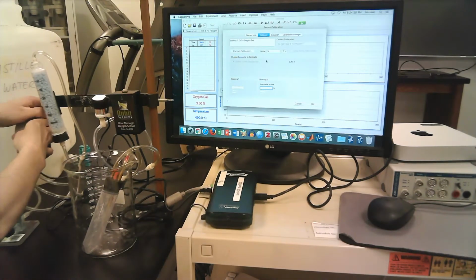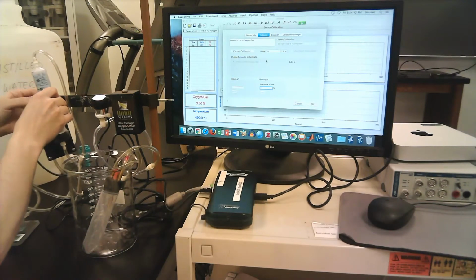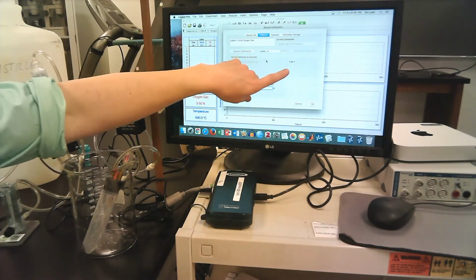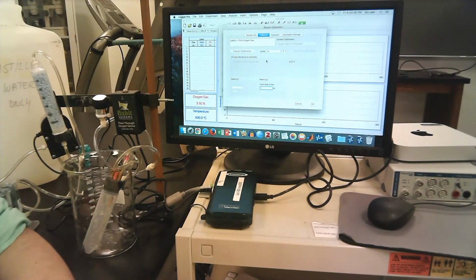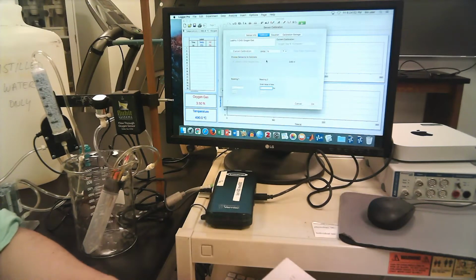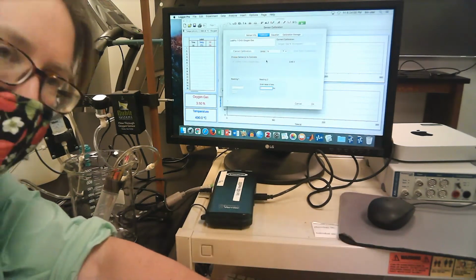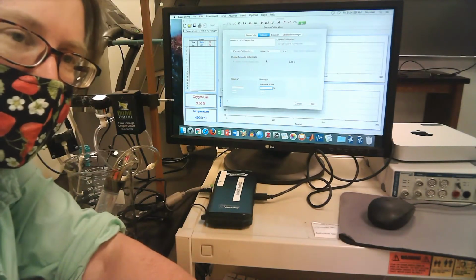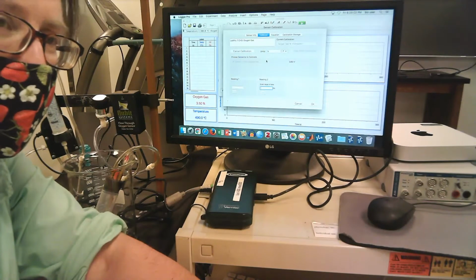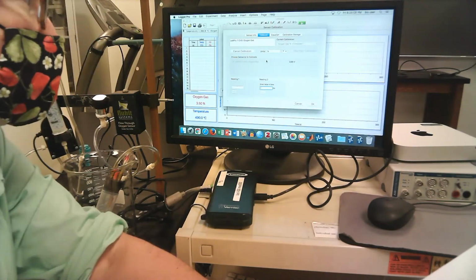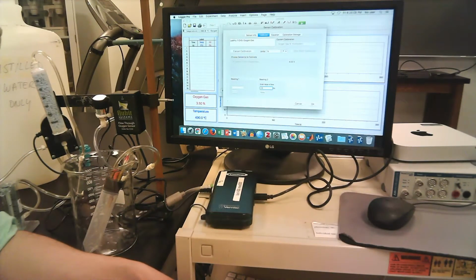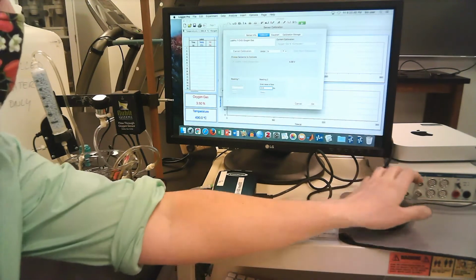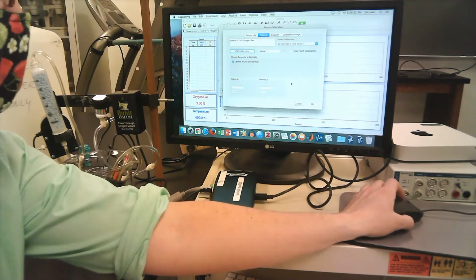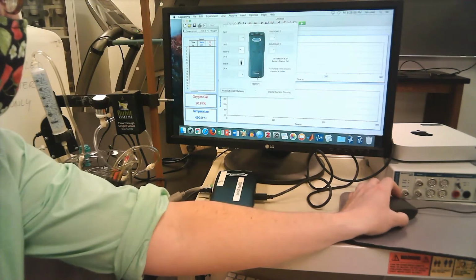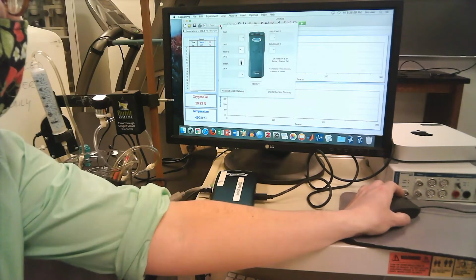Maybe I'll hang this back up again so it doesn't make as much noise. Okay, and what you should see is now this voltage reading is starting to climb up. So again, I'm going to just wait for a little while until that voltage reading starts to stabilize. And then you're going to want to enter in the concentration of oxygen in the air as your second reading, right? So that's going to be 20.95, or in this case, we can just enter in 20.9. So I'm going to type in 20.9. Okay, that's looking stable, so then I can press keep. Okay, and then my oxygen analyzer is calibrated. So I can close out of that window.